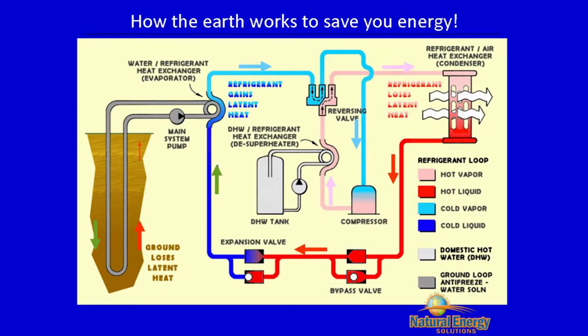When we come out of that compressor, we have hot gas. In the thermodynamic sense, it's actually called a superheated gas. The very first thing we can do, DHW stands for domestic hot water, is strip a little bit of that energy away to heat your hot water for the house. We take enough energy to heat the hot water, but not so much that we can't still heat the house.